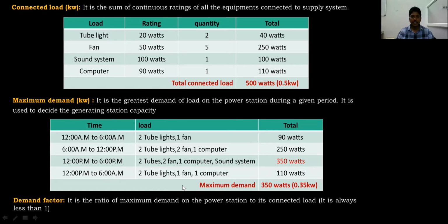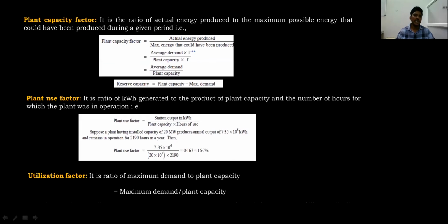And demand factor: out of the connected load, how much demand the consumers are having is called the demand factor. Demand factor is equal to maximum demand divided by connected load. This is the connected load I have connected to the power plant, as well as the maximum demand in the day. This gives you the demand factor, the demand the power plant is getting from loads. Here it is 70%, so only 70% of the connected load's demand is being drawn from the power plant.